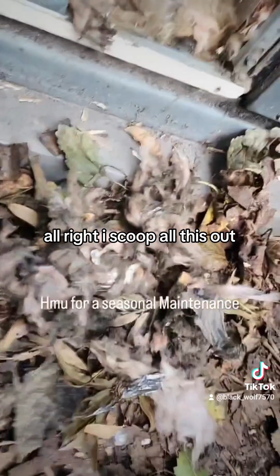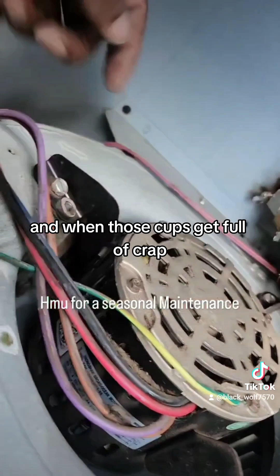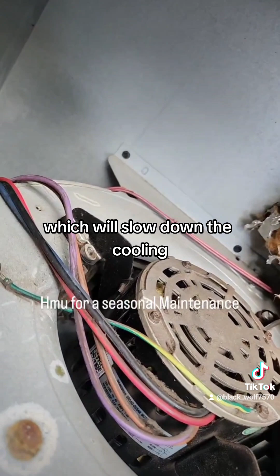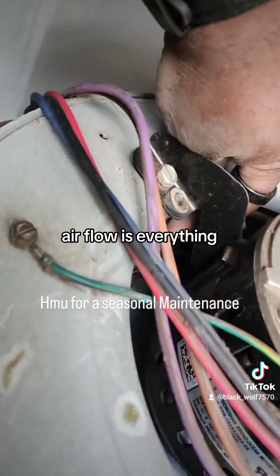A little fan motor on the bottom, actually. There's two sides of this fan motor, or two sides of this wheel. So think of a bunch of cups like this in line, shaped just like this, like a hamster wheel. And there's a whole bunch of them. And when those cups get full of crap, it can't throw air properly, which will slow down the cooling, slow down the heat, cause overheating, freezing, all that other stuff. Airflow is everything. So you got to make sure this is clean.